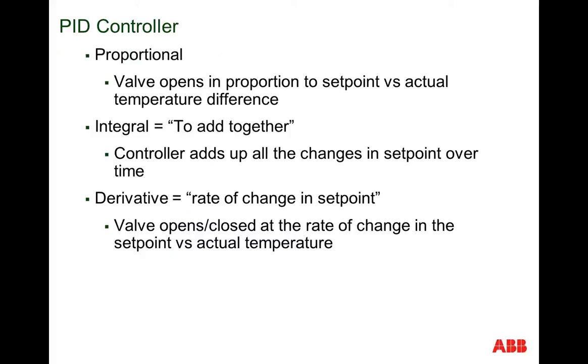Hence, we design smarts into the controller, and we can turn on, turn off, and tune these three parameters to match the unique physical characteristics of the application. For proportional control, the valve will open in proportion to the set point versus the actual temperature difference. For integral control, the controller will add up all the changes at set point over time. And then finally, for derivative control, the valve will open and close based on the rate of change in the set point versus the actual temperature. So this makes for smarter control.